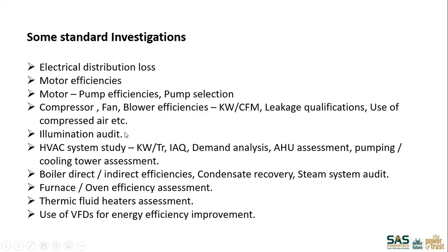Illumination audit is carried out many times. In large industries, your energy consumption on illumination is also comparatively high. HVAC can be analyzed for kW per TR, indoor air quality, demand analysis, AHU. All these things can be considered. For boilers, direct and indirect efficiencies, condensate recovery, and steam system audits can be done. Furnaces and ovens can be assessed for energy efficiency in terms of consumed kilocalories or consumed kWh per ton of manufacturing or per piece, whatever that furnace is doing, depending upon the type of furnace.